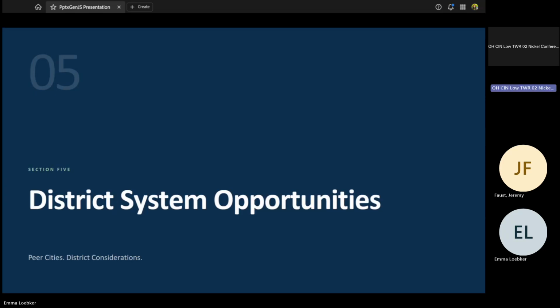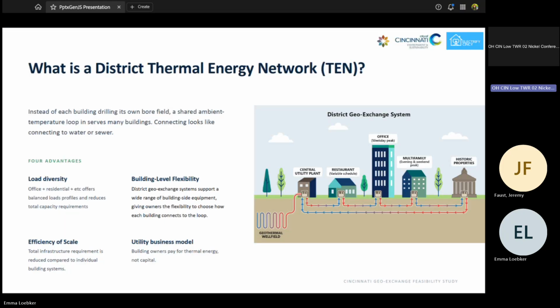Okay, so district systems. I'm excited about this piece. When it comes to district systems, what really differentiates this from building level applications is the number of buildings you're interconnecting onto one geo-exchange system. A lot of times these are called district thermal energy networks. It's not too different in concept from distributing chilled water, hot water, or steam. But in a geo-exchange application, you're distributing an ambient loop, or neutral temperature loop, with water or fluid essentially the same temperature as the ground. Each individual building then pulls off its respective heating and cooling needs from that loop.